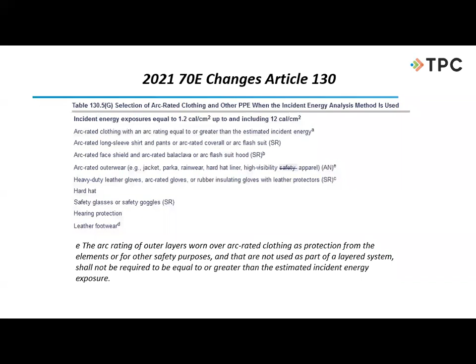Also in 130.7C1, here we are going to try to establish an electrically safe work condition, but the estimated incident energy is greater than what the clothing is that I can go purchase. But the clothing you can go purchase now is getting quite high. I've seen arc flash suits up to 175 calories, so they're getting up there. But let's say you don't have that at your facility, and you have incident energy of 54 calories, and you don't have any clothing that could meet that requirement.